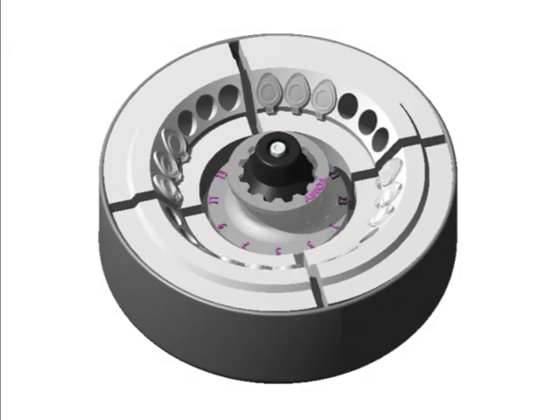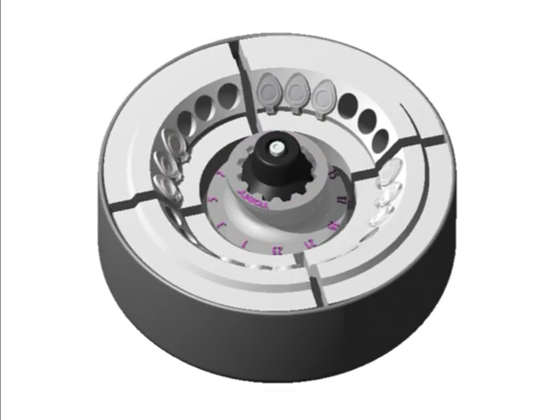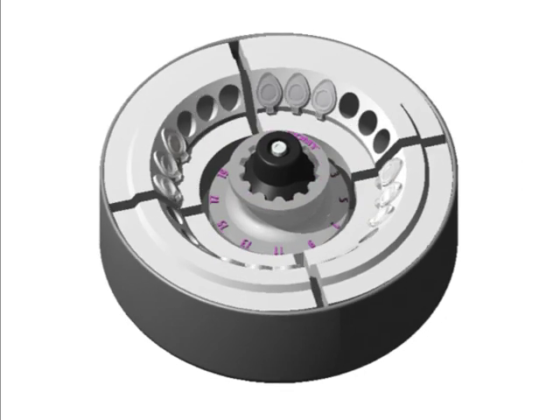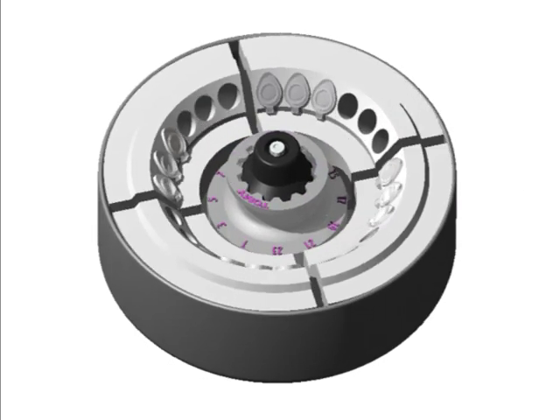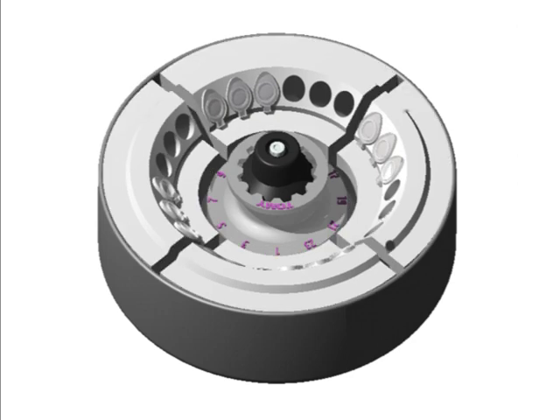Spinning begins. As you can see, the rack is getting firmly attached to the rotor wall as the speed of rotation gradually increases. Let me show you still images of this innovative racking rotor system at spinning and stopping for comparison. Now you see, this mechanism comprises a segmental rack that allows the rack to be firmly fixed to the wall of the rotor housing.